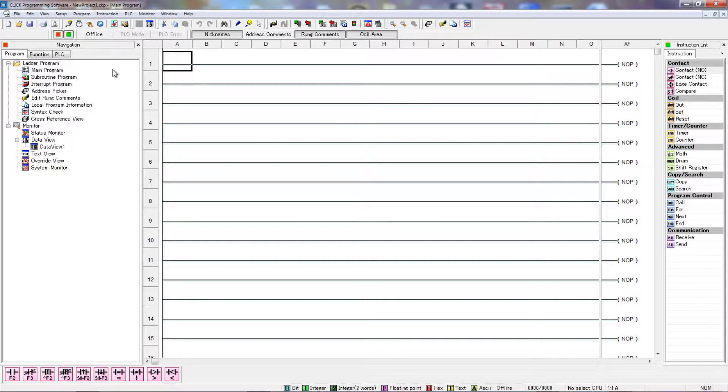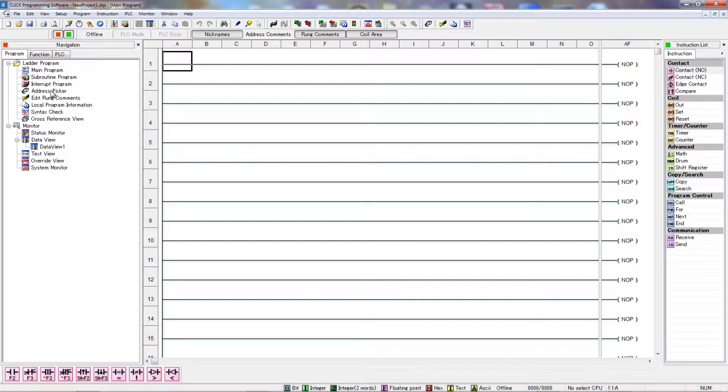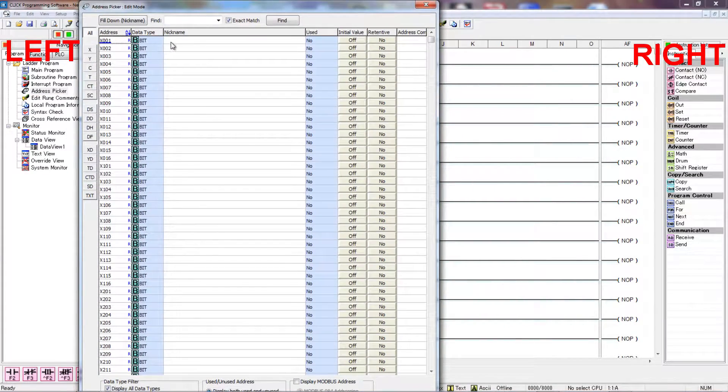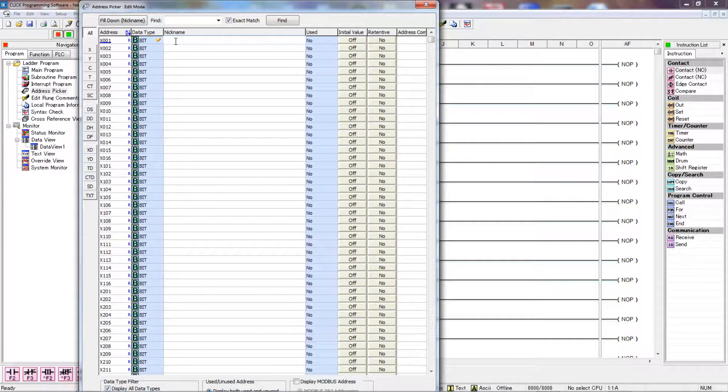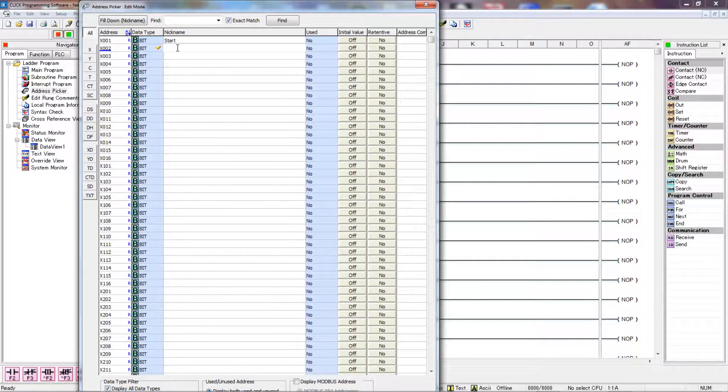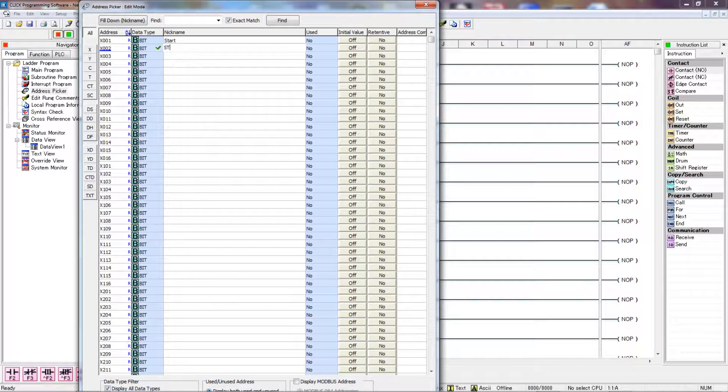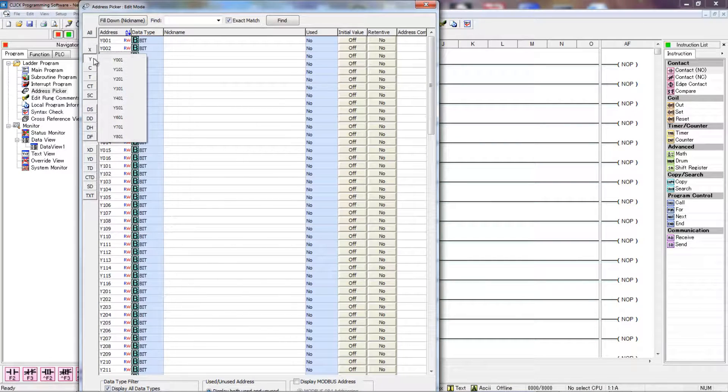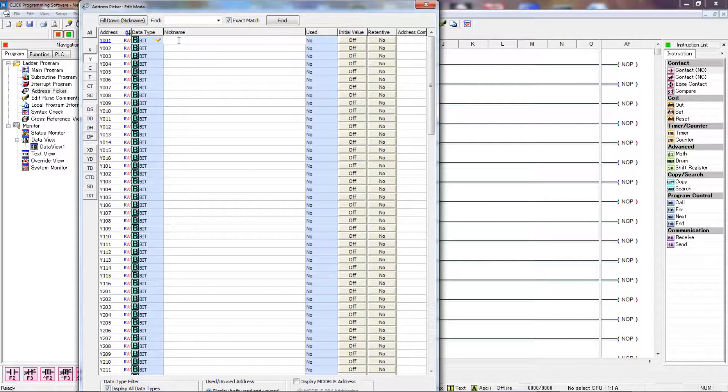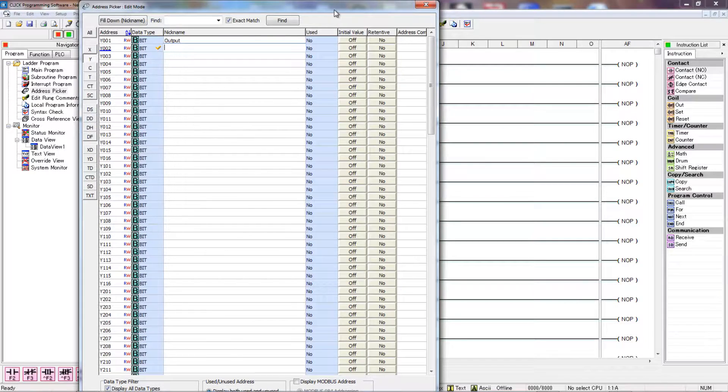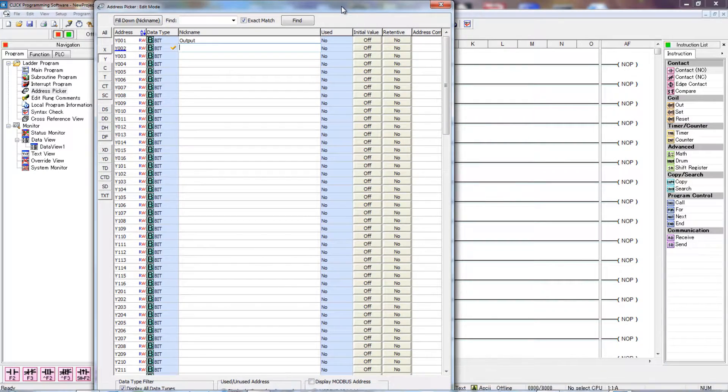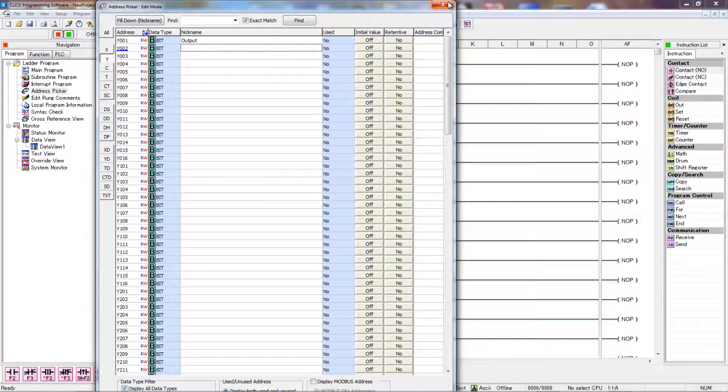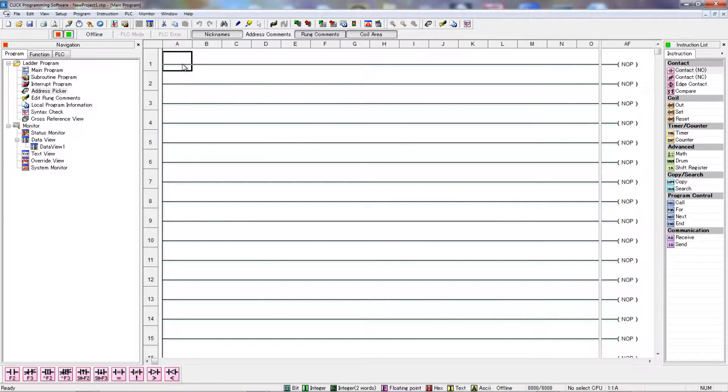So I'm using AutomationDirect's Click programming software with a Click PLC to demonstrate the start-stop seal circuit. To begin with, the first thing I usually like to do is go to the address picker up here in the upper right-hand corner and allocate the I/O. So for a start-stop seal circuit, we're going to need a start button. These X's are inputs, and so these will be wired to real-world inputs. I'll include an electrical diagram as well, and this will show how these are hooked up. X2 is stop. And then over on the Y, we have the outputs. So for Y001, I'm just going to call it output. And we'll have that hooked up to a pilot light. So I'm going to hit OK there, and then we'll start our ladder programming.